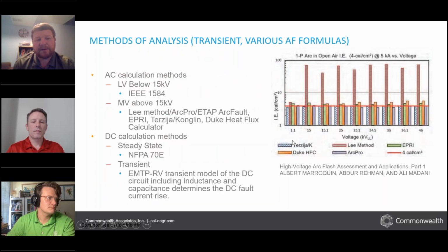Yep. So when it comes to low voltage, that's 15 kV and below, 1584 is the go-to for the industry. So there is one method. I wouldn't say that method is conservative. That is the industry standard method. When you get above 15 kV, there is a lot of discussion, and there's been no IEEE based empirical study to look at higher voltage arc flash calculations, but there's been a lot of industry standard studies that are accepted out there. And this graphic that we have is a good example of that.